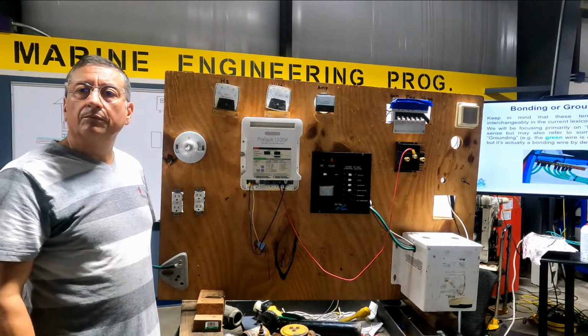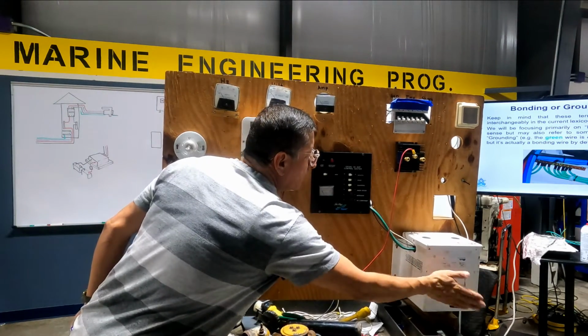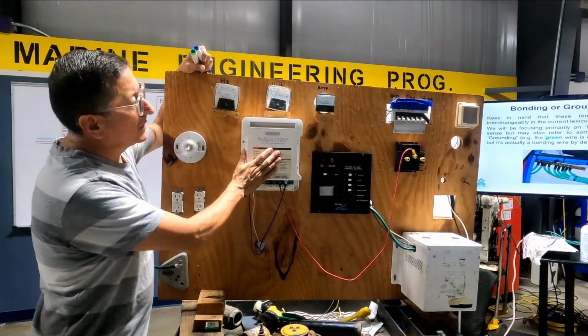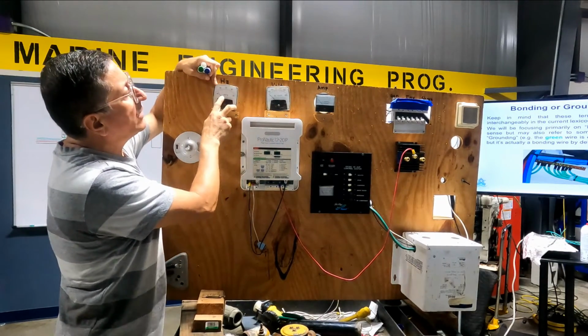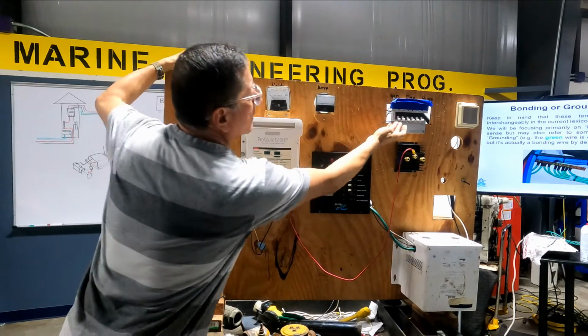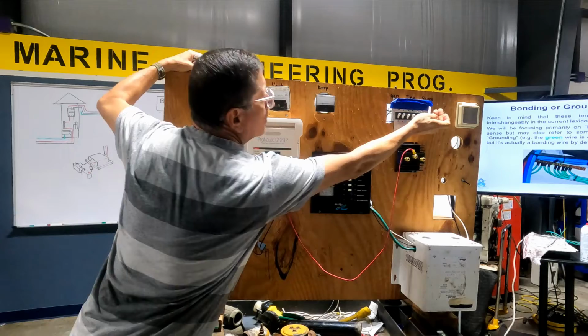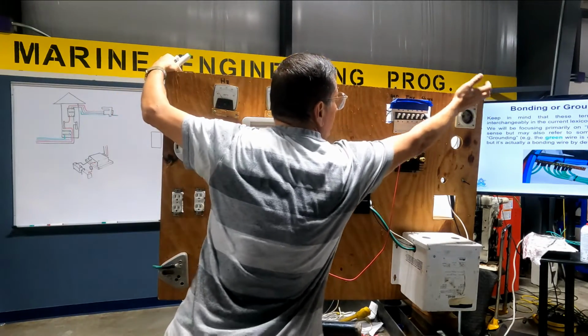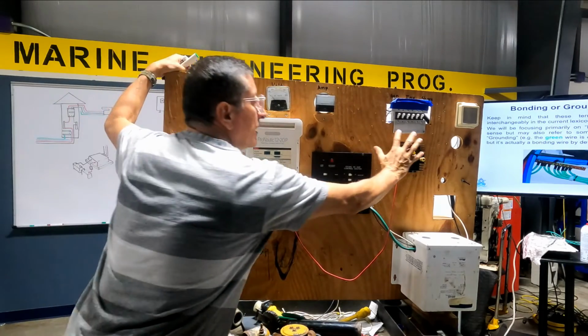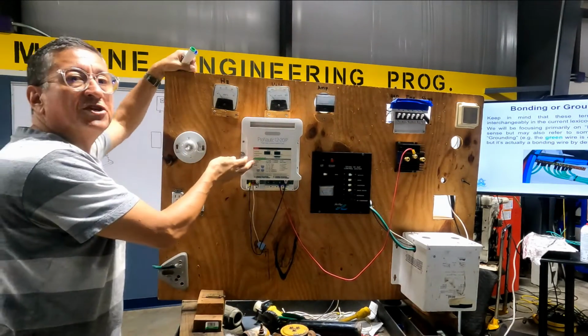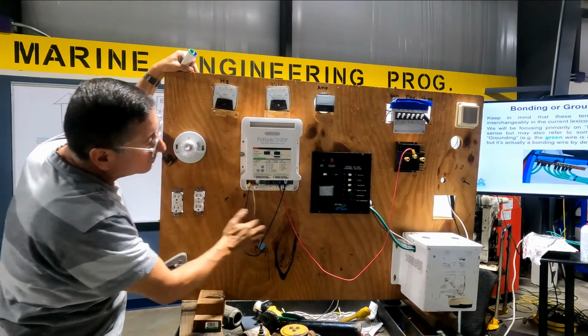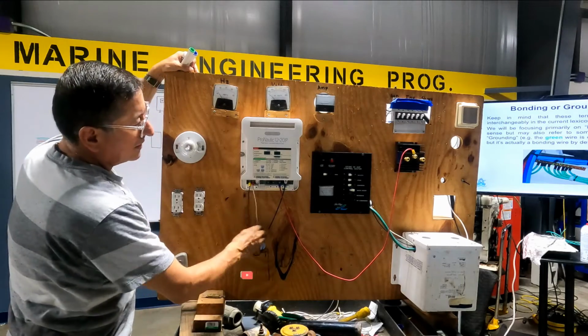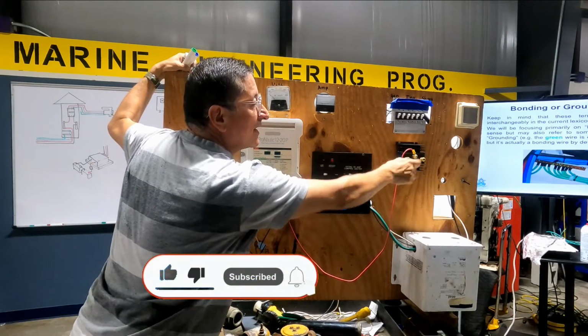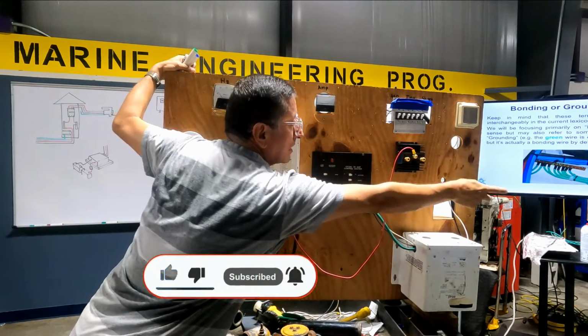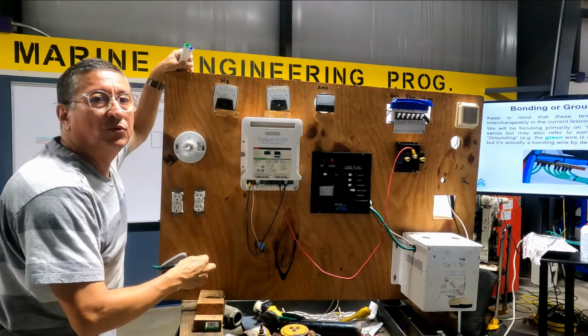That's the panel. We have the isolator transformer and the battery charger. We have three meters: volts, frequency, and amps. And we have the three breakers: generator, inverter, shore power. And we have the shore power connection. This is an ACR. The ACR is related with the battery charger. The battery charger receives hot and neutral from one breaker, and the output is DC. The output enters the ACR, and the ACR has two outputs: one output for battery bank number 1 and another output for battery bank number 2.